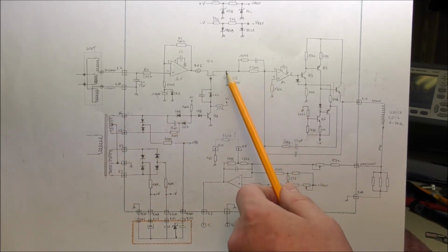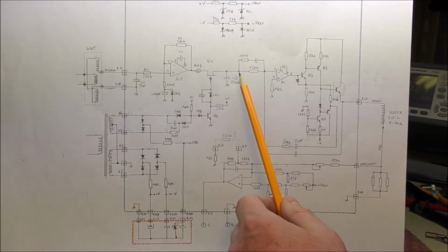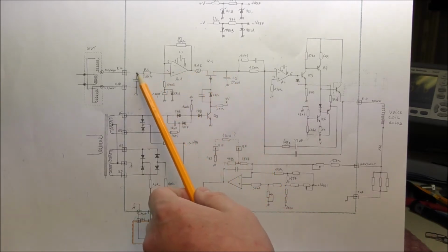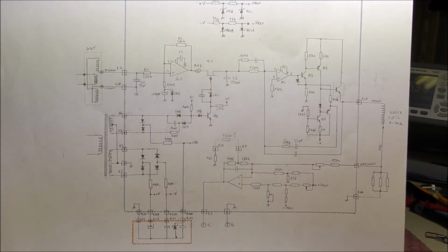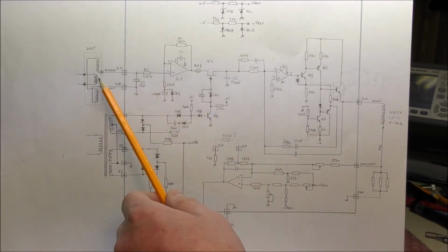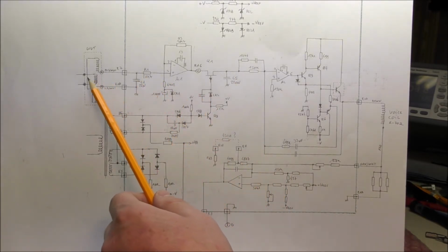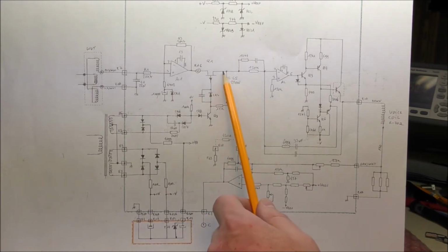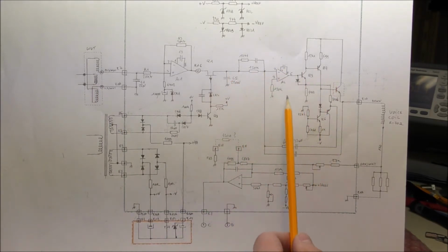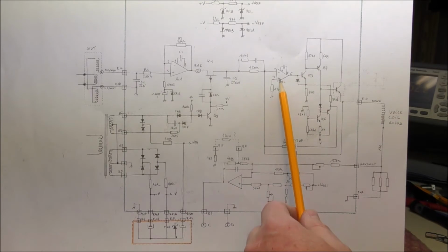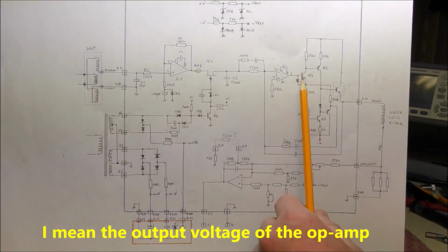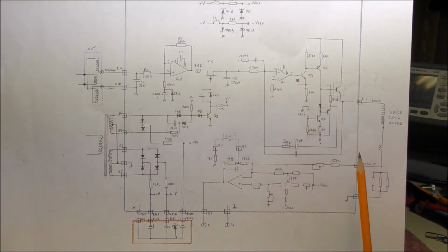So at this output we have a DC signal which is proportional to the AC voltage at this input here. So the goal is to have 0 volt, of course, here in order to have a 0 position of the LVDT sensor. This error signal is fed to this error amplifier, which is made around this op-amp here. This op-amp is fed to this power buffer here, and you can see that the feedback is only this capacitor. This is an integrator actually. So the gain is very high at DC, so this permits to have a very small error.